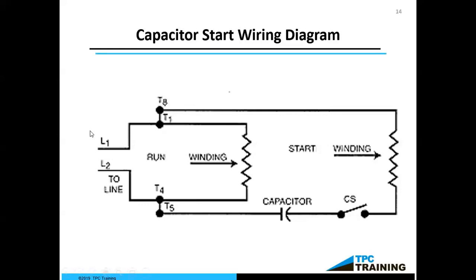We don't want any vertical or horizontal play. And then one of the last things I'm going to do is put an ohm meter on L1 and L2. This is before I even install the motor, because it will give me a resistance of what the motor is when it's just sitting there. So we would be reading straight through the one run winding. Probably couldn't read through the capacitor, but it would tell us if the run winding is good or bad.